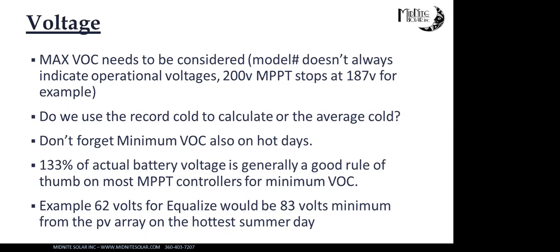And when I say the actual voltage, I'm talking about the target. So if you have a flooded acid battery and you want to equalize to 61 volts, you need 133% of 61 volts for that controller to turn on. Well, I guess you see down there where I said 62 volts would need 83 volts actual on the hottest summer day. So those are a couple things to keep in mind. Our string sizing tool takes that into account pretty well, but you always want to think about that.